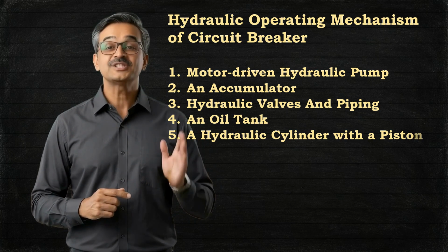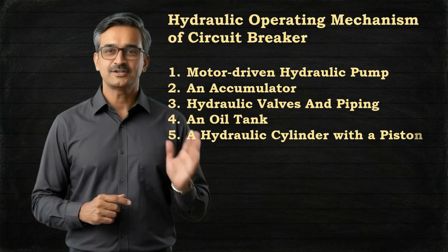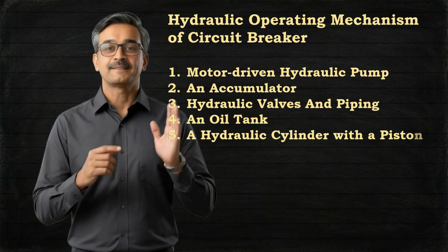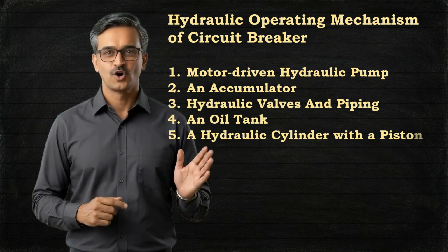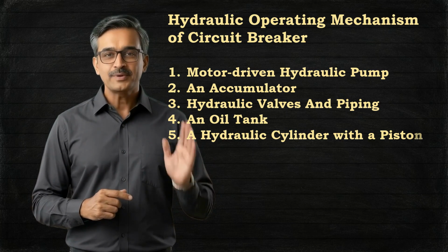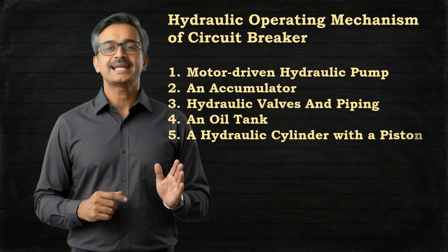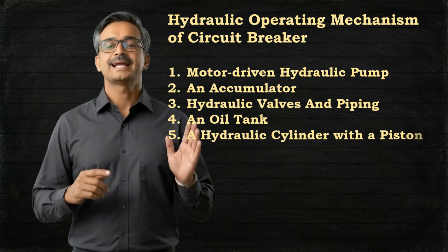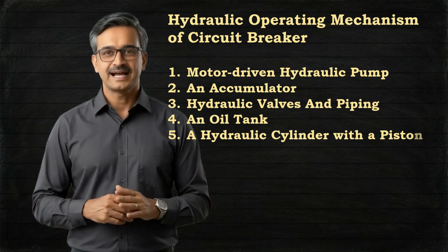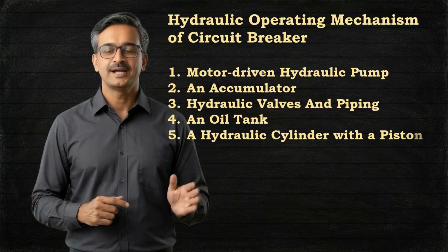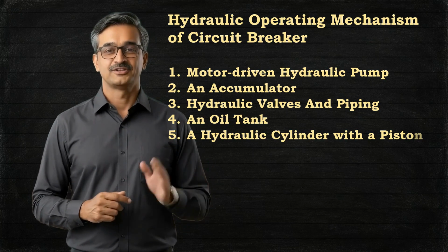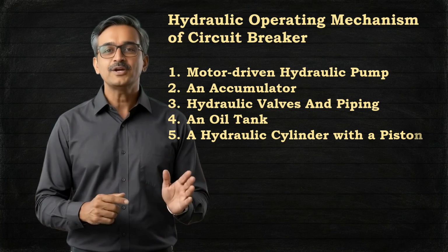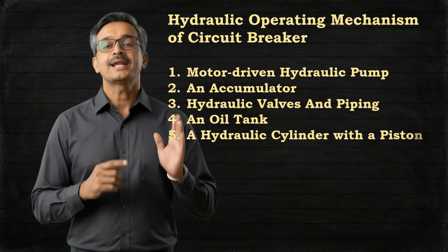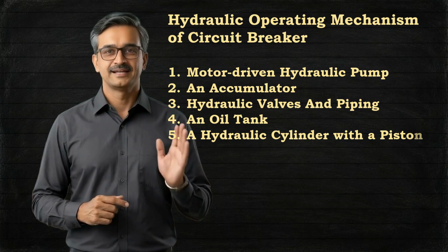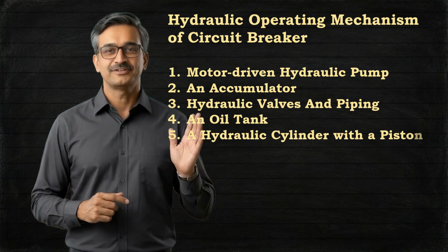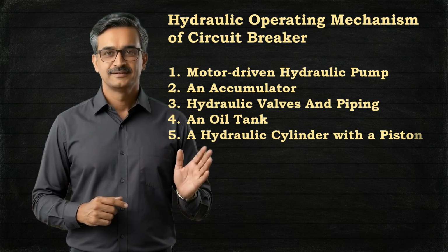During the opening operation, the hydraulic oil is directed to the upper side of the piston. This forces the piston to move in the opposite direction, thereby opening the circuit breaker. The main advantage of the hydraulic operating mechanism is that it can provide very high-speed closing and opening operations without significant bounce or vibration. This is because the highly pressurized hydraulic oil naturally provides damping to the dynamic mechanical system of the circuit breaker during its operation.